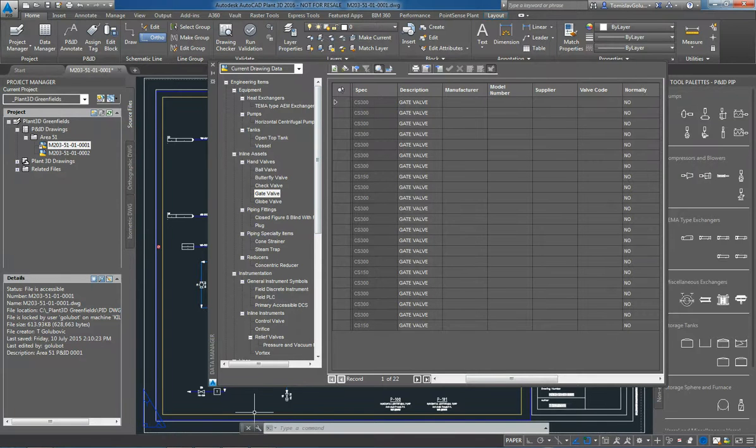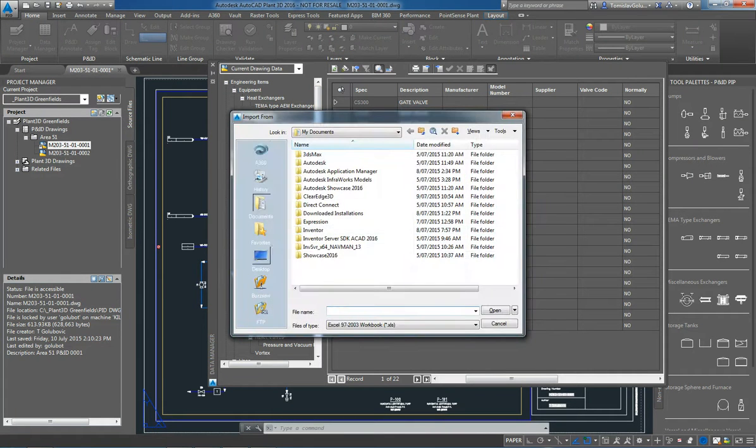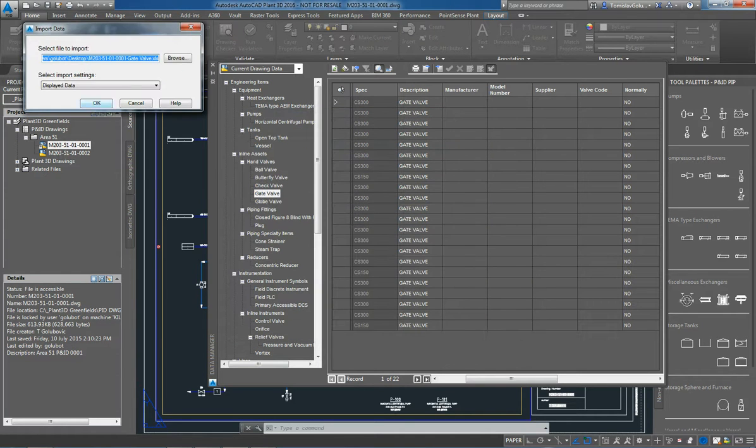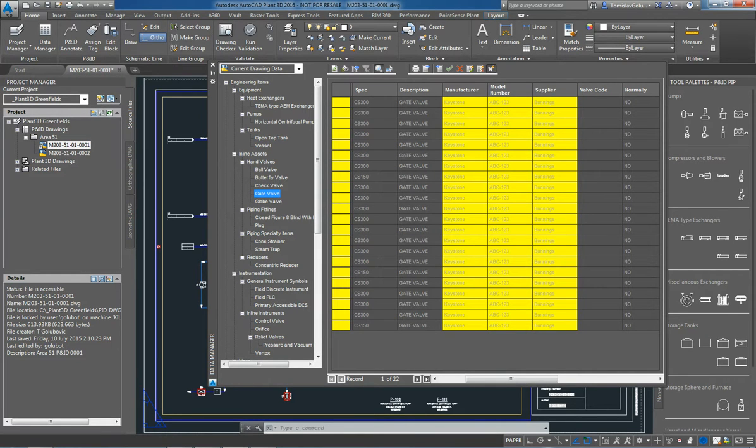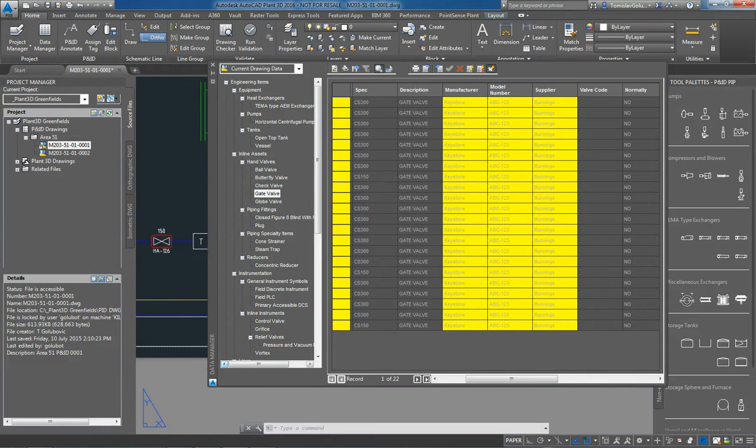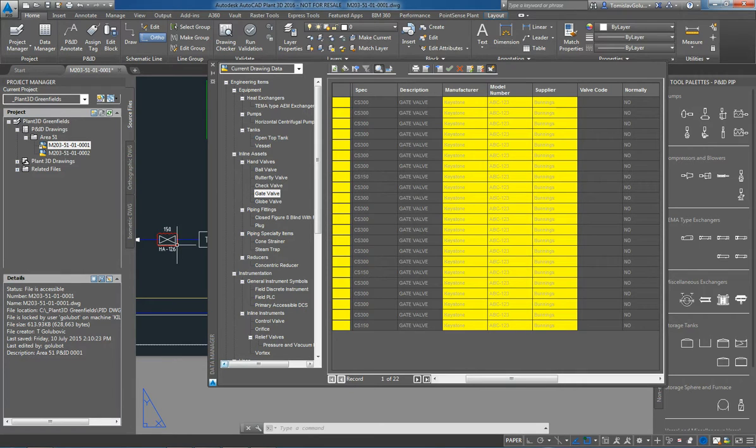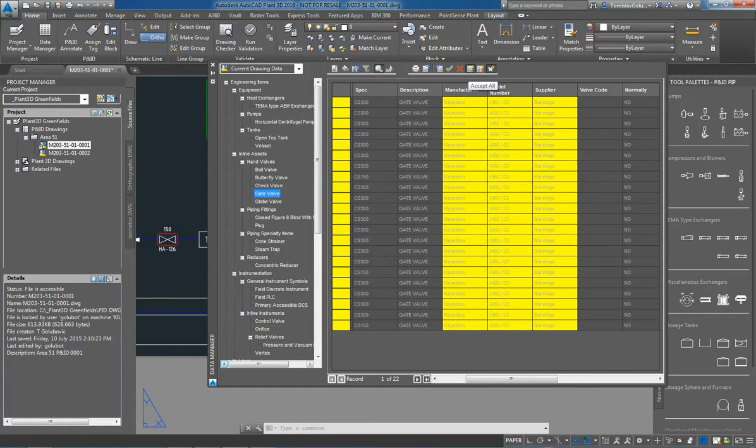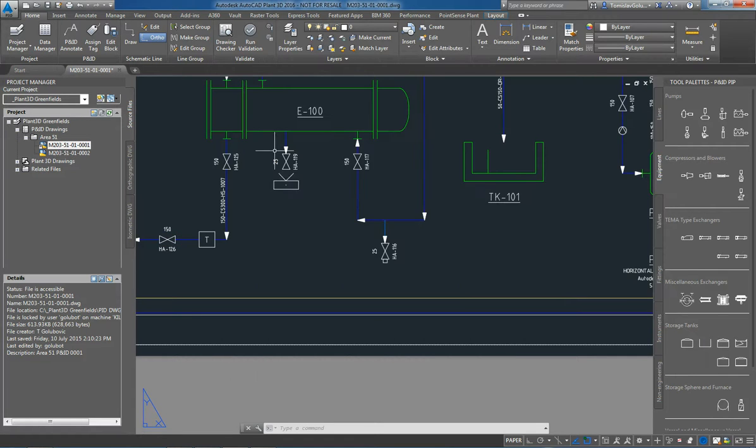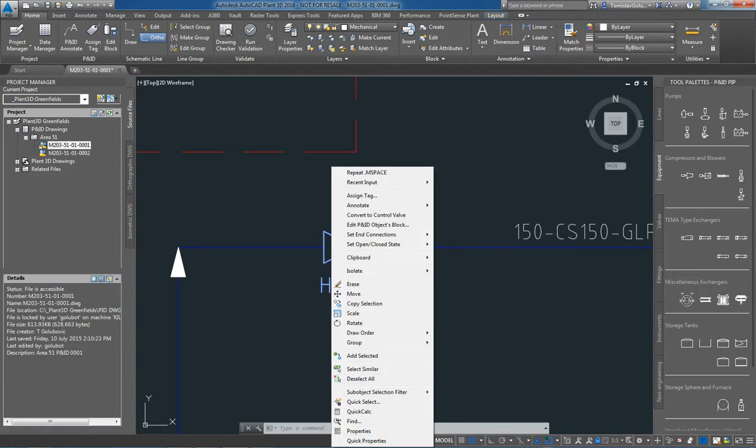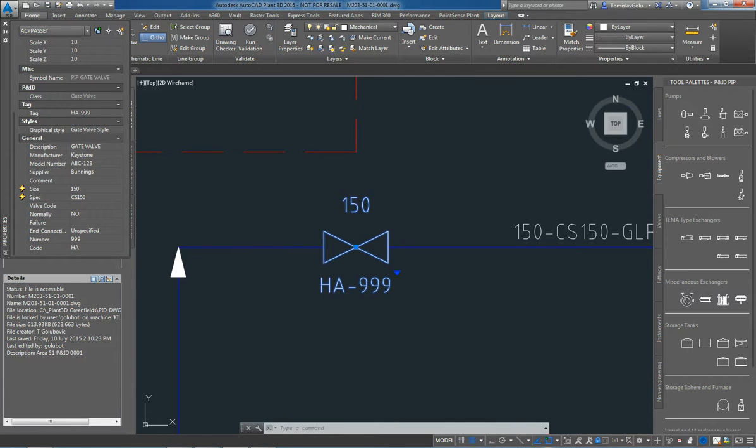I go back to Plant3D or P&ID and I import that file. So now I select that same gate valves list. And now it's telling me that we have these Keystone valves here. And if I zoom to part of the P&ID, you can see there that the valve has been clouded. I can turn those clouds on and off. I can also accept or reject these changes one at a time or I can say do all of them. So I'm just going to say yes to all of them. Then the data gets committed to the database. It's writing it to that P&ID. And just as a check, I can even pull up one of the other P&IDs, the other valves. Have a look at the properties of it. And we can see there that we have Keystone ABC123 and that we're buying it from Bunnings.